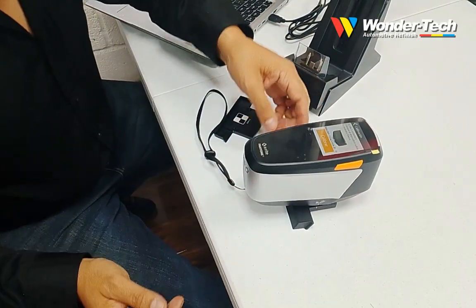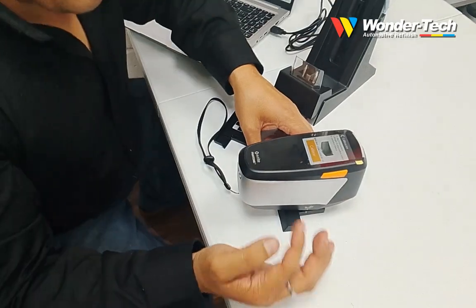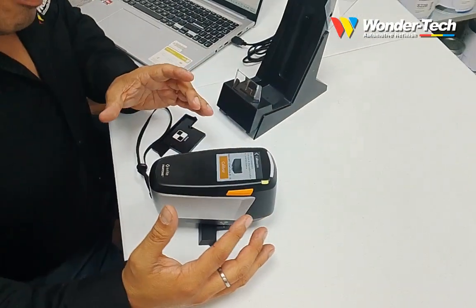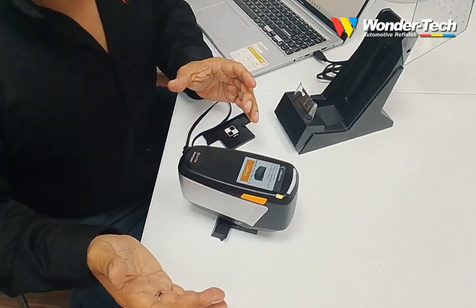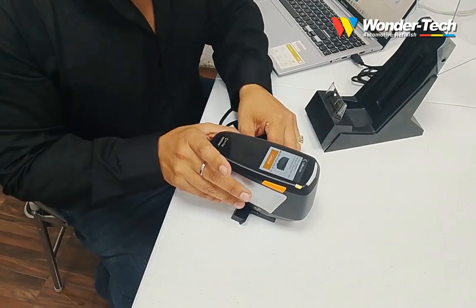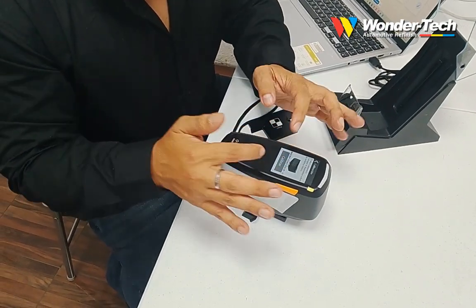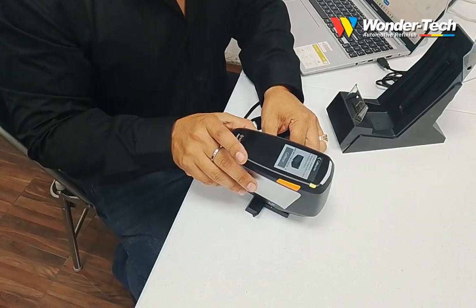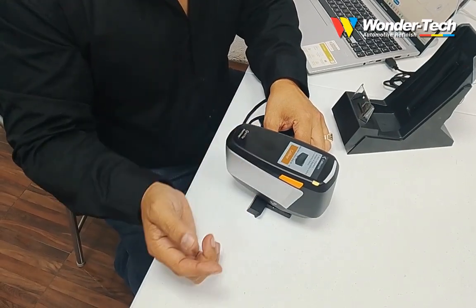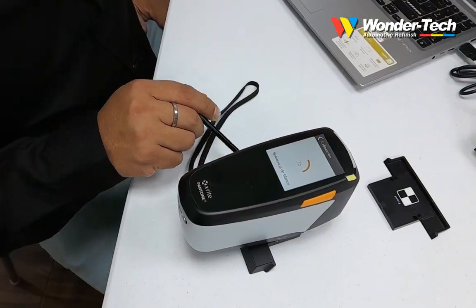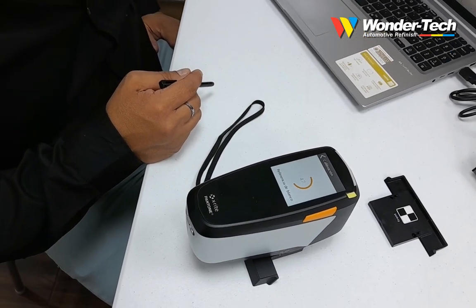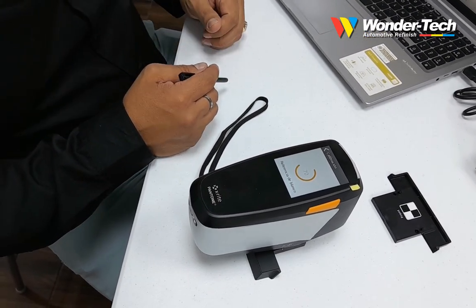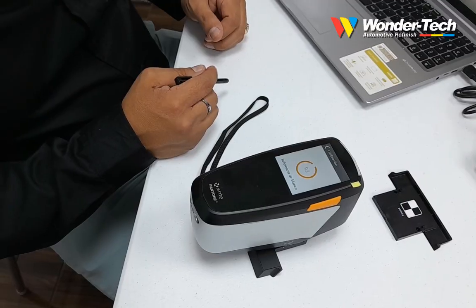Once the calibration tile is correctly positioned, the calibration indicator changes to orange. If the tile is not seated properly, the button remains gray and calibration cannot begin. When the indicator turns orange, simply press Calibrate. The instrument will automatically perform the calibration sequence. A progress indicator will display while the process is running.